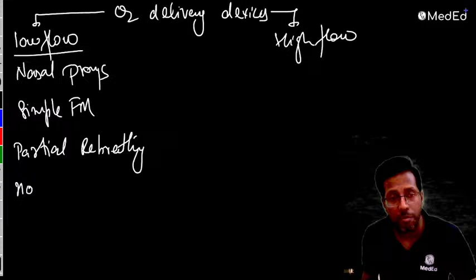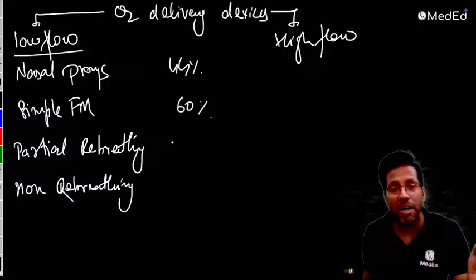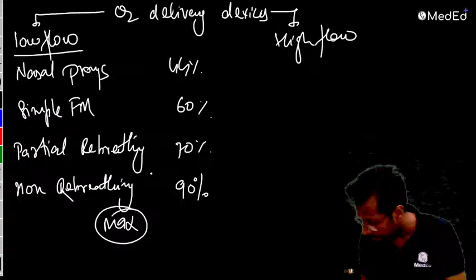Right. So maximum FiO2, a nasal prongs works between 1 to 6 liters and the maximum is 44%. Simple face masks work between 5 to 10 liters, the maximum is 60%. Partial rebreathing works between 10 to 12 liters, the maximum is 70%. Non-rebreathing works between 12 to 15 liters, the maximum is 90%. Out of all the low flow devices, the maximum FiO2 is given by the non-rebreathing mask.